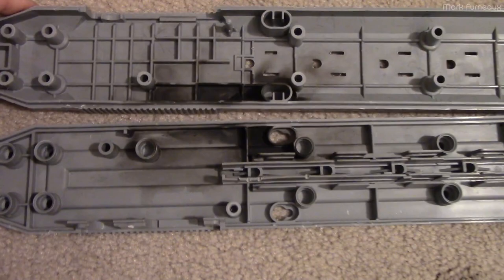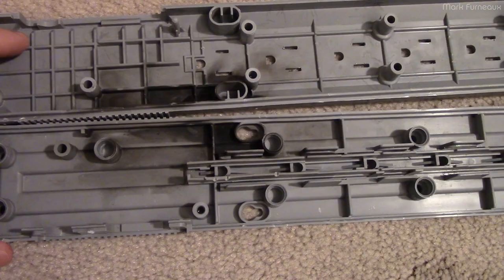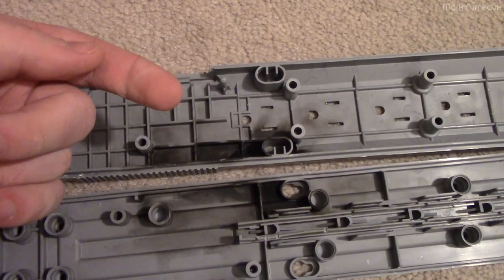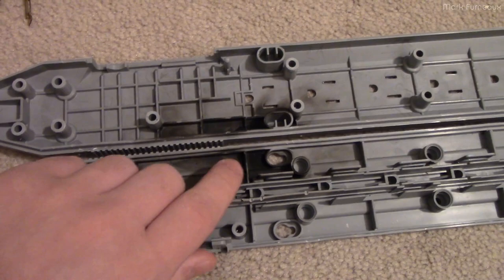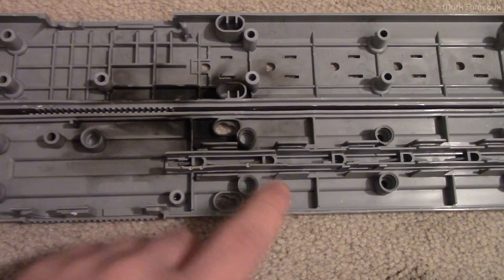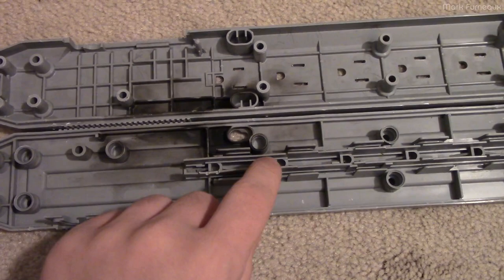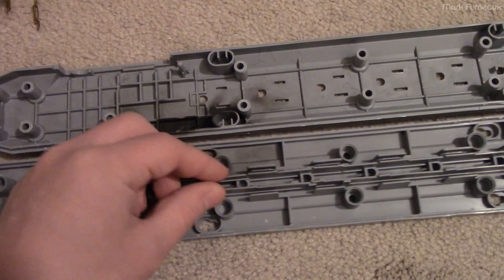So this is pretty much certainly lightning damage, when you look at the circuitry. But this is what it looks like after I cleaned it. And this stuff, even though it's soot — it's carbon — it doesn't rub off. That's because this was superheated in an arc flash and it's actually melted itself into the plastic. So this doesn't come off. This is after I cleaned it. The only case where the carbon matters is around the channels for the bus bars, and that I've cleaned out, so there's no carbon tracking issues.